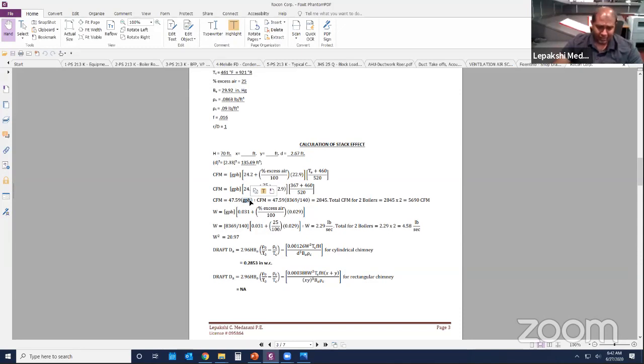If you put in all that information, you'll calculate how much flue gas is coming out from that mechanical equipment room. In this case, those two boilers give 5,690 cubic feet per minute of flue gases. So you determine this CFM amount.